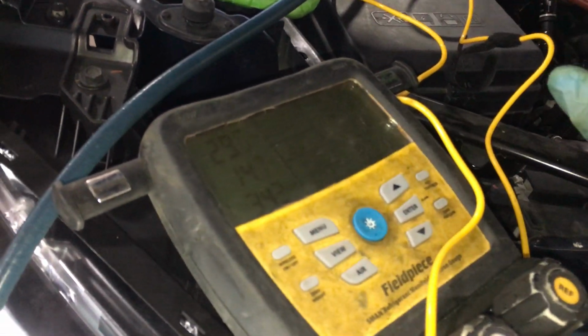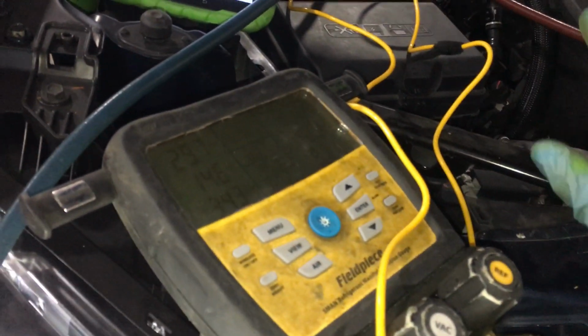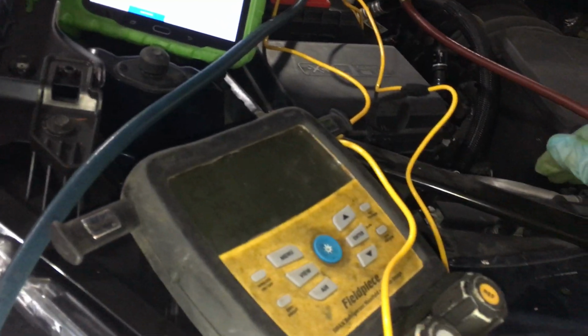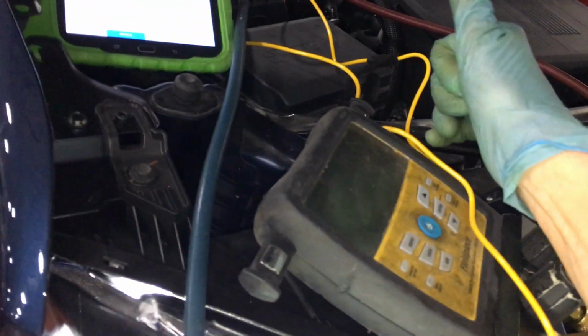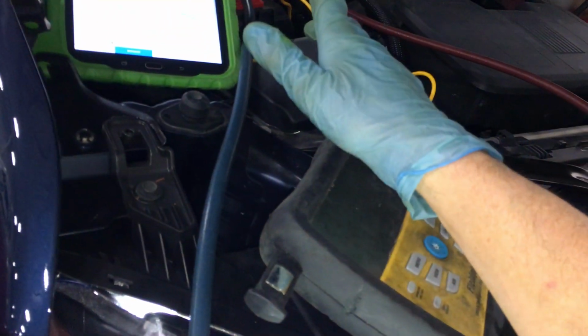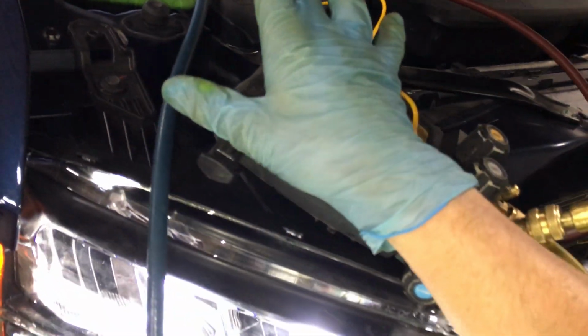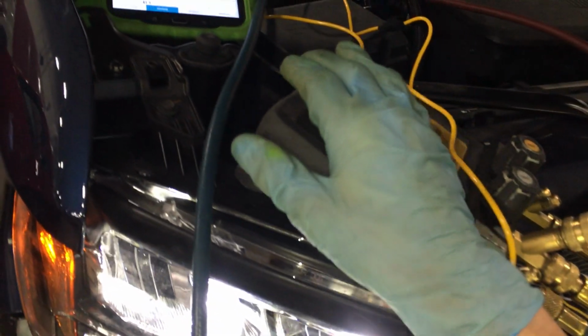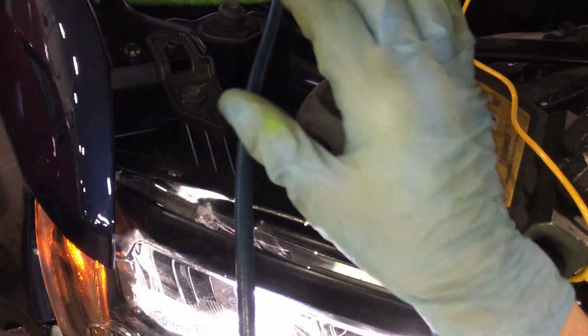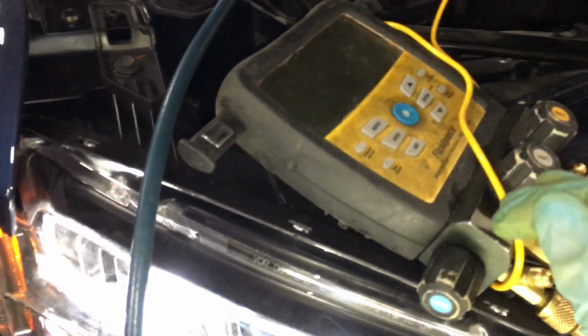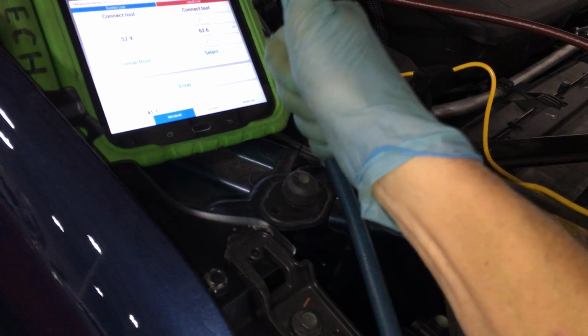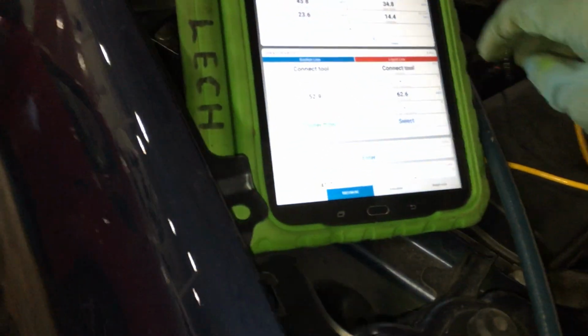I don't know how many times I have to say this. Get it out of your head. It's that old basic rules of, you know, all refrigeration or air conditioning is the same. Not once you start adding variable speed compressors, variable speed blowers, variable speed condenser fan motors, all that basic stuff you were taught in school. Kind of hold on to it, but basically take it and drop that book in the garbage can. You got a new set of rules to learn, and the rules of thumb is not one of them. You use a rule of thumb, I'll cut your thumb off.